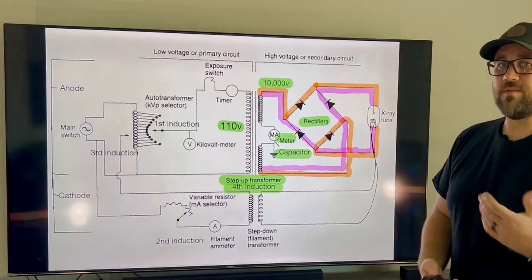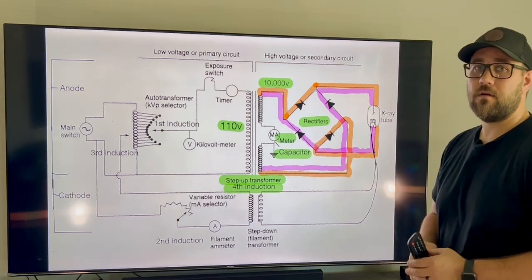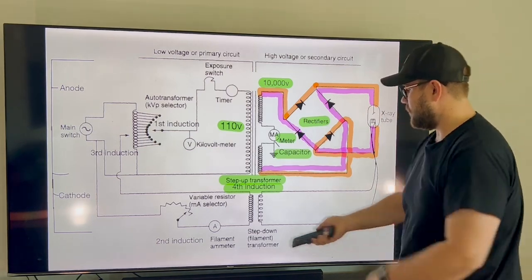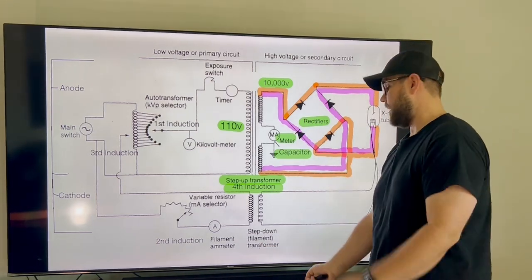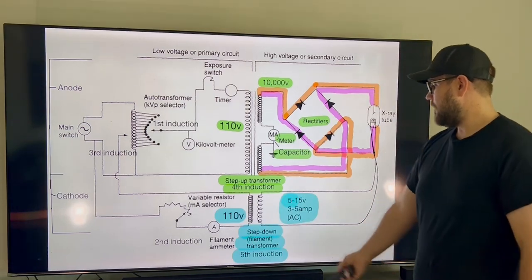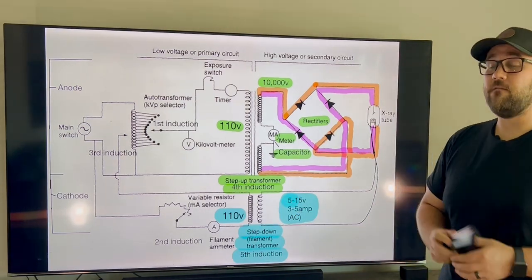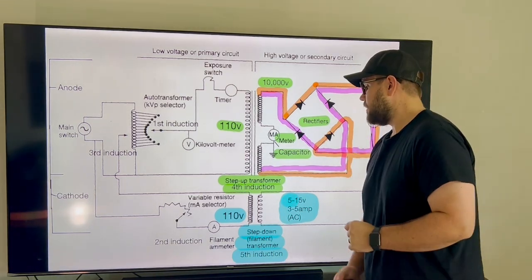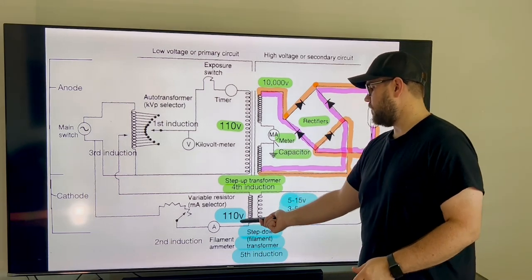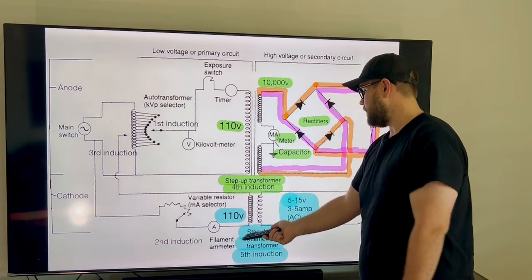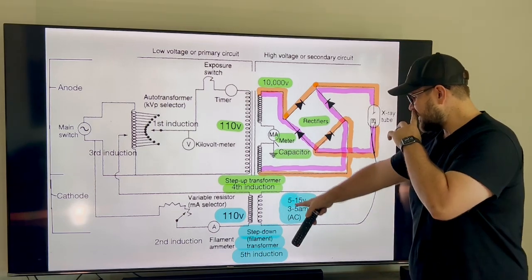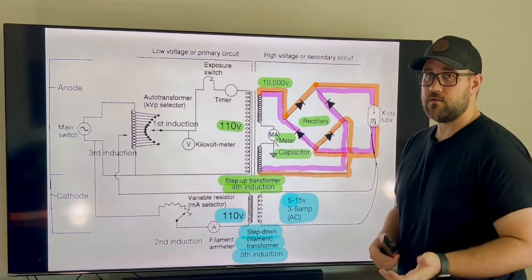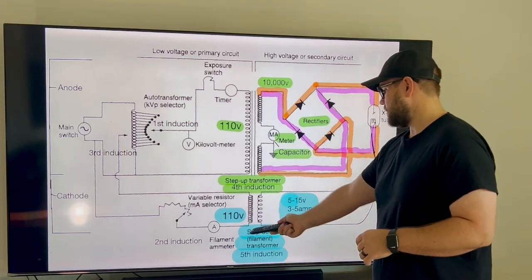Now that our anode side has kind of been talked about, we understand how we went from one side to the other, got our 110 volts to our 10,000 pulsating DC. Let's go back to our last induction that I want to talk about on this page, and that's going to be our step-down, the filament transformer, which will be our fifth induction and our last one talked about on this page. So it's going to take our 110 volts alternating current, and it's going to step it down, so more coils to less. It's going to step it down to 5 to 15 volts. It'll also have 3 to 5 amps, but this also will be alternating current. And again, this is our step-down.